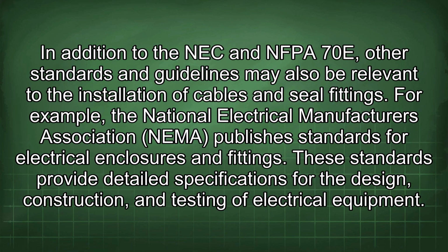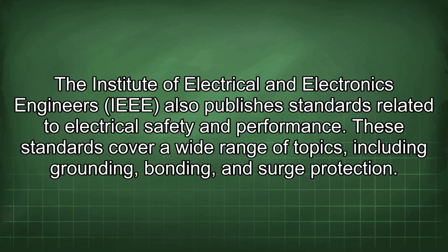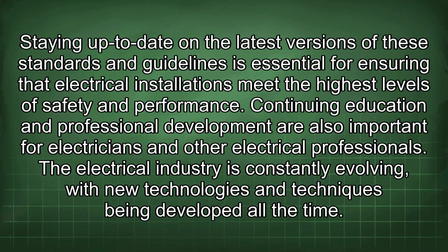installation techniques. In addition to the NEC and NFPA 70E, other standards and guidelines may also be relevant to the installation of cables and seal fittings. For example, the National Electrical Manufacturers Association, NEMA, publishes standards for electrical enclosures and fittings. These standards provide detailed specifications for the design, construction, and testing of electrical equipment. The Institute of Electrical and Electronics Engineers, IEEE, also publishes standards related to electrical safety and performance. These standards cover a wide range of topics, including grounding, bonding, and surge protection. Staying up to date on the latest versions of these standards and guidelines is essential for ensuring that electrical installations meet the highest levels of safety and performance.